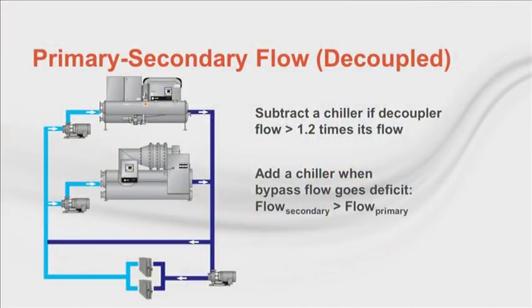It has 1 or more chillers, typically in parallel, with at least as many pumps as chillers, a secondary side pump or pumps, and a bypass line that decouples the flow through the chillers from the flow through the air handlers or terminals. The secondary flow varies because there is no bypass at each coil. Instead, 2-way modulating valves open or close in response to load. The flow through the chillers is different than the flow through the building or process, and the surplus or deficit flow automatically flows through the decoupler bypass pipe.